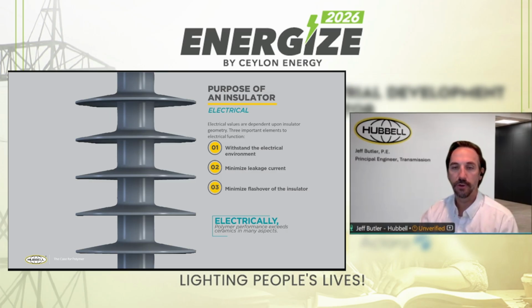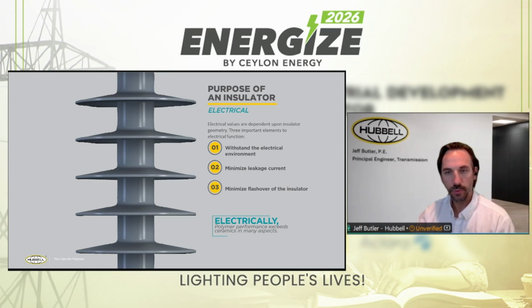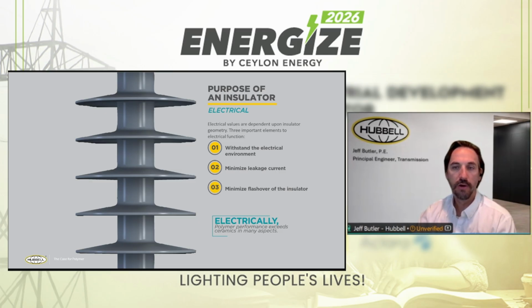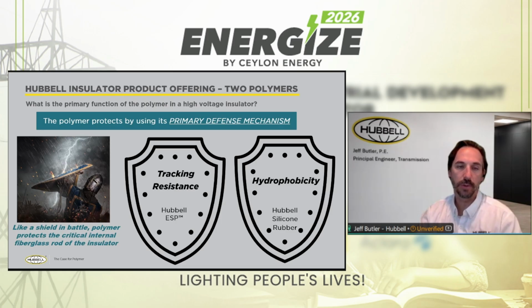All the while maintaining their mechanical strength and integrity. So when we're talking polymer insulators, talking composite insulators for Hubbell, there's actually two different types of materials that we use to achieve protecting the fiberglass rod. So the primary function of the polymer, as I mentioned, is to protect the fiberglass rod. So we can look at it as kind of a knight going into battle or a soldier going into battle. The arrows that could be attacking that soldier are the environment. It's the electrical activity, even mechanical stresses. So all those different activities that are occurring in the environment of an insulator are trying to destroy that insulator.